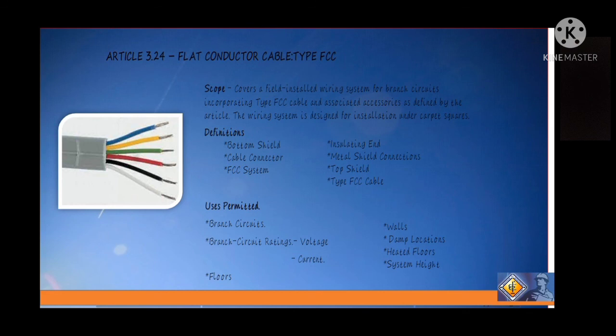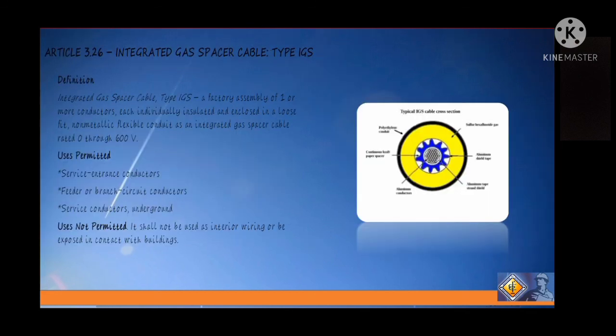So in terms of uses permitted, it is used for branch circuit, in branch circuit ratings including voltage and current, in floor, walls, damp location, heating floors, and system height. So in Article 3.26, which is the integrated gas spacer cable, or the type IGS. So IGS is a factory assembly of one or more conductors, each individually insulated and enclosed in a loose fit non-metallic flexible conduit as an integrated gas spacer cable rated 0 through 600 volts.